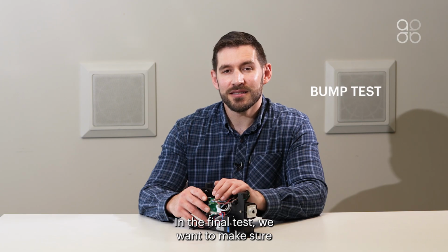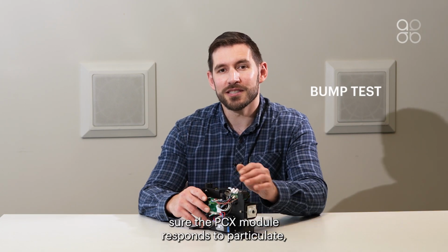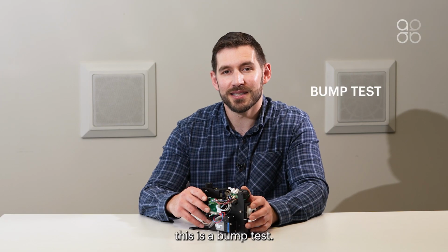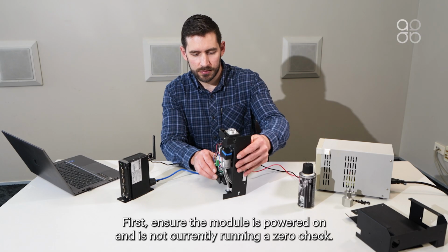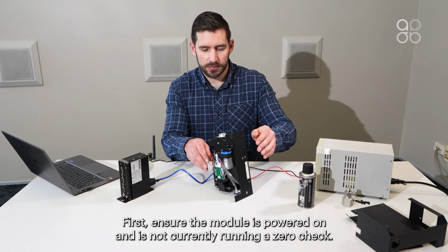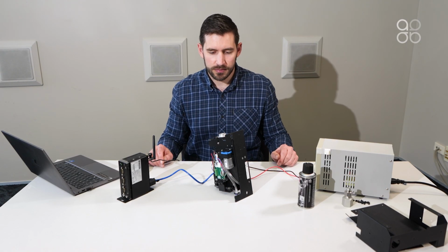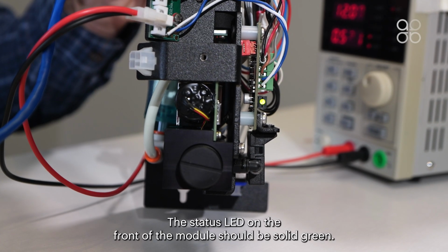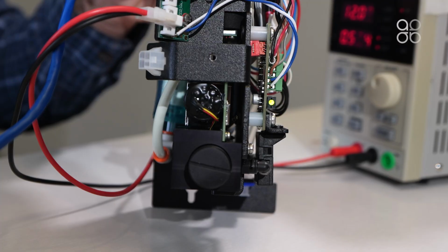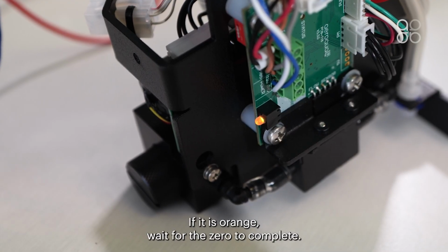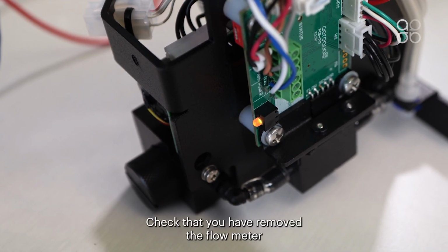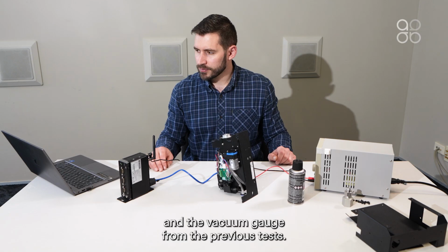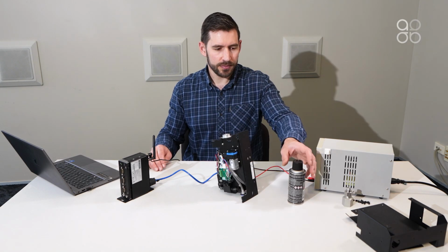In the final test, we want to make sure the PCX module responds to particulate. This is a bump test. First, ensure the module is powered on and is not currently running a zero check. The status LED on the front of the module should be solid green. If it is orange, wait for the zero to complete. Check that you've removed the flow meter and the vacuum gauge from the previous tests.